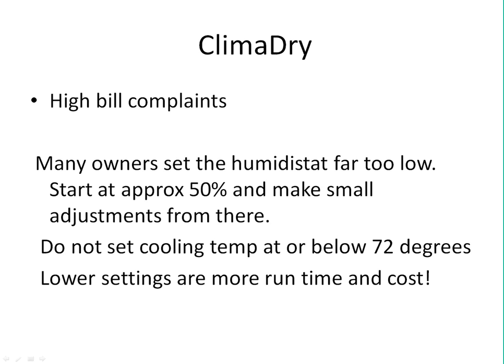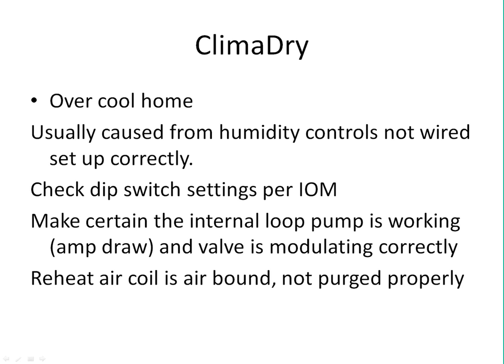So if you get a high bill complaint and it's involving a ClimaDry, one of the first things I want to ask them is, what are your settings? Both humidity as well as your cooling. Another one we oftentimes get is it's overcooling the home. It's usually caused from the humidity controls either not being wired up correctly or set up correctly. Sometimes not being operated correctly. You also want to check those dip switch settings per the IOM for that ClimaDry.